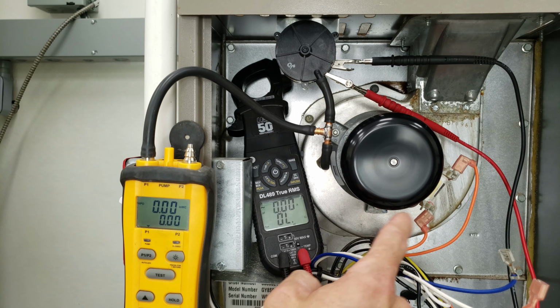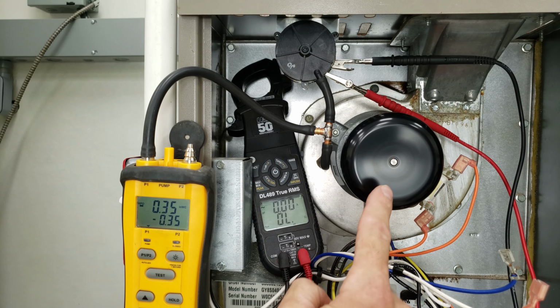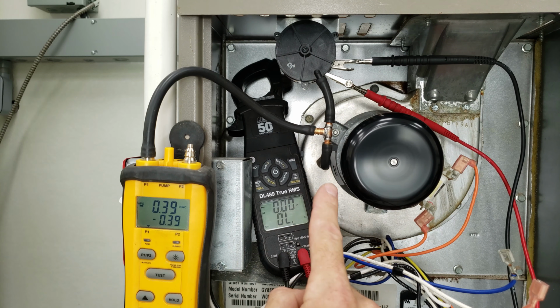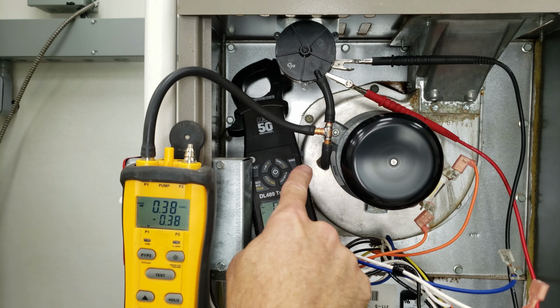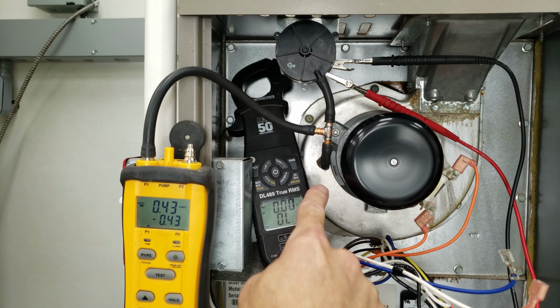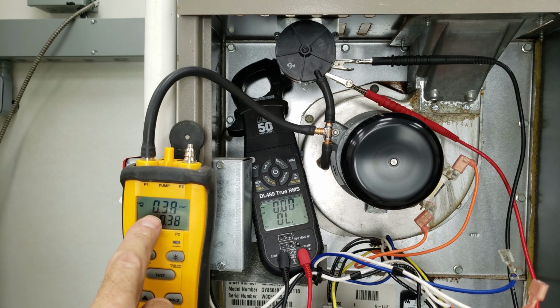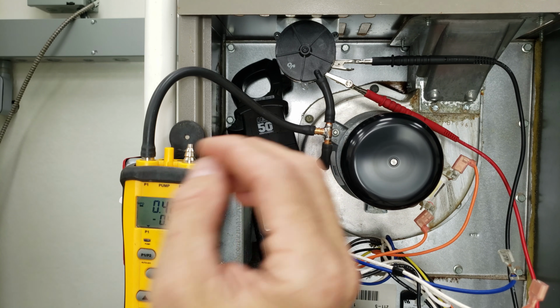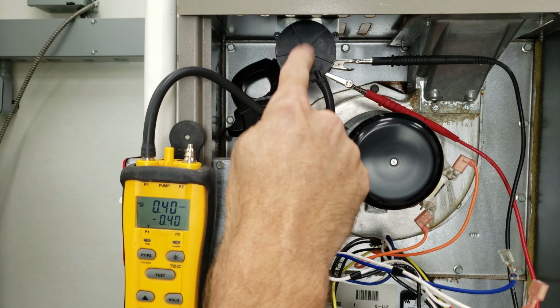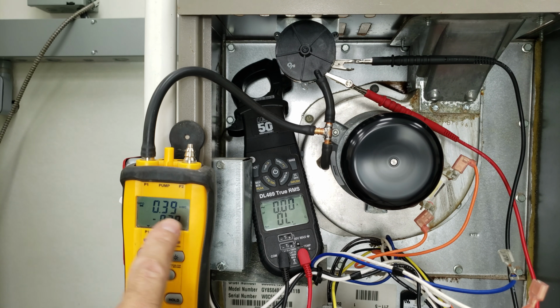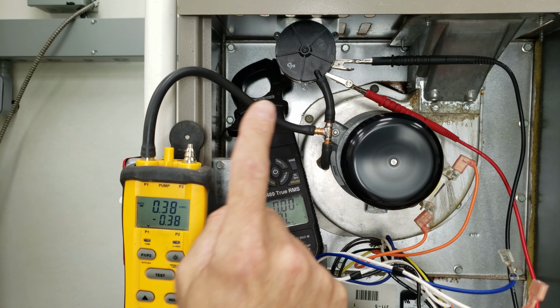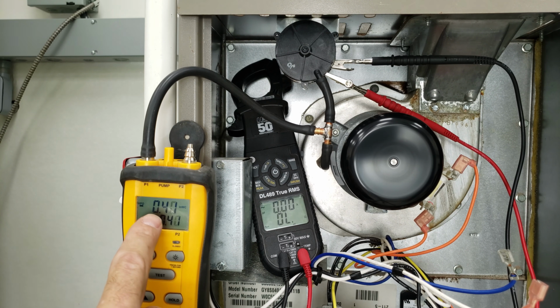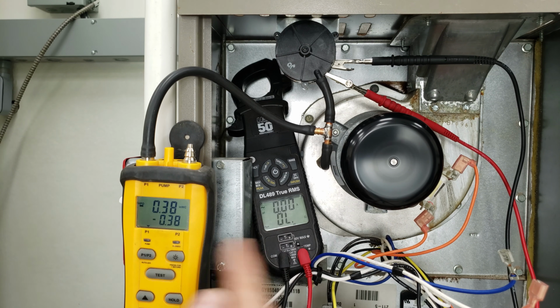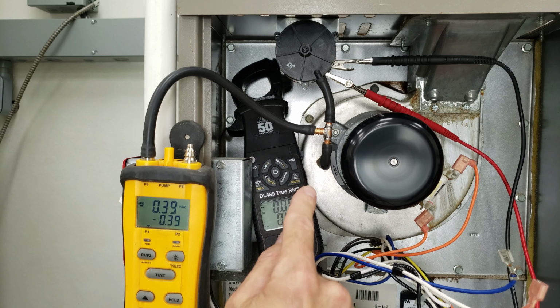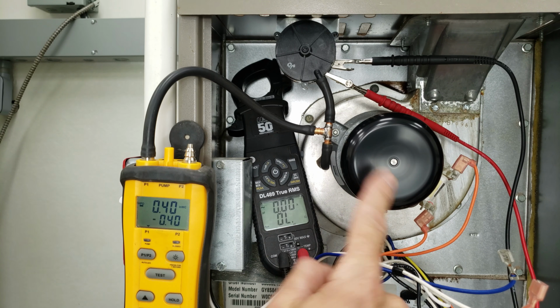So the first thing that should turn on is the inducer motor. And the job of the pressure switch is to make sure that the inducer motor is running and there's no clogs in the tubing. And so you see we're measuring a water column pressure, which is the pressure reduction on this side of the switch, and we're only measuring 0.39 or 0.42, so that's not enough. It should be a lot higher of a pressure reduction, so maybe about 1 inch water column. So we know that there's an issue, but we do see our inducer motor running.